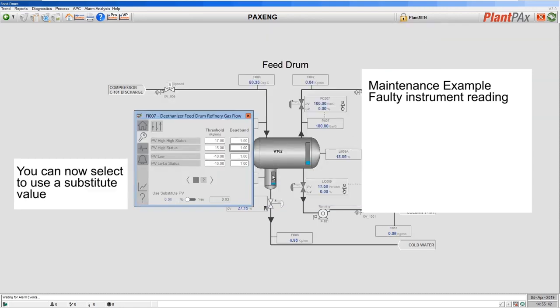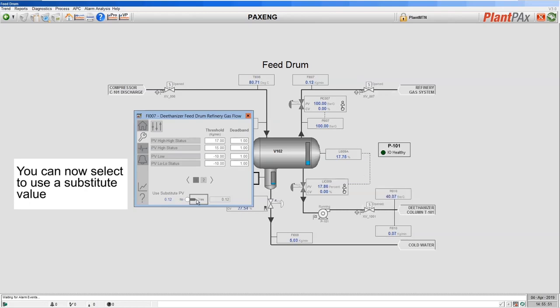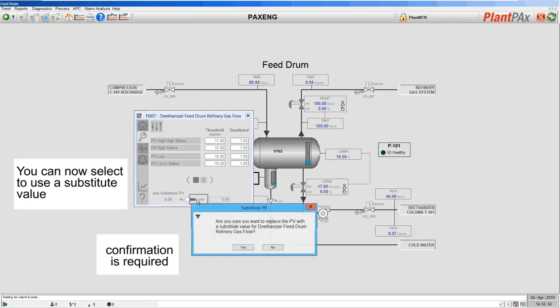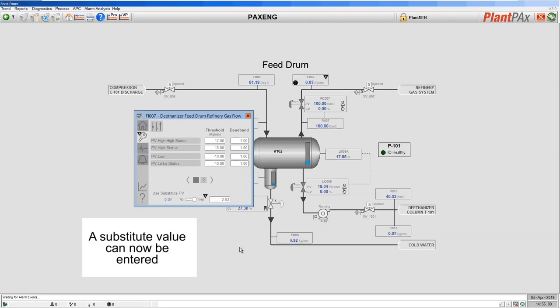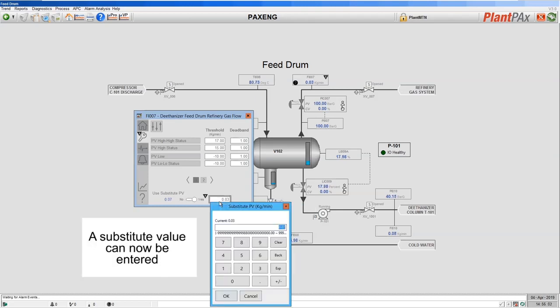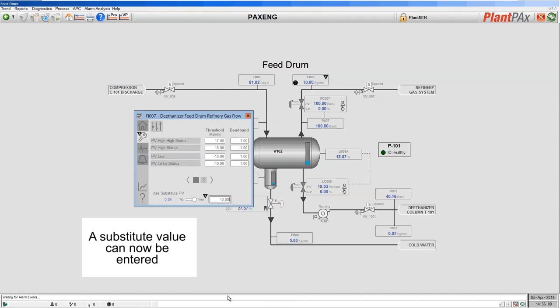Now I've logged in as that higher-level user and I have the ability to decide whether I want to use the real analog input being measured from the field, or if I wish to substitute it. Let's go ahead and substitute the value for this analog input. I'm asked to confirm that I want to do this, and once I've selected yes I can then enter a substitute value. I can now put in a suitable value that gets my process going — there's no need to open up the engineering tools for the controller and go online to apply forces in the code; I can do everything I need from the HMI.